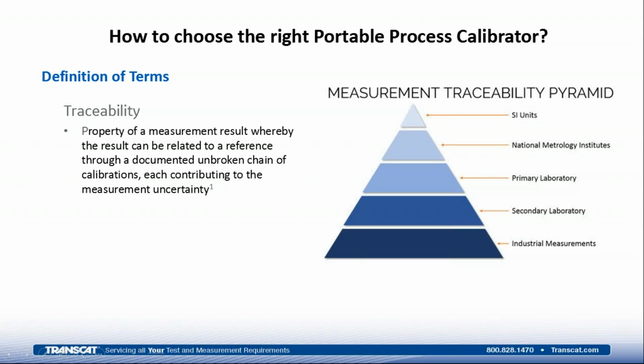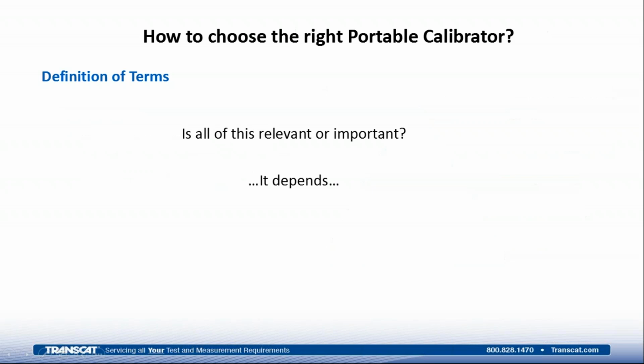Now, those units and devices will be calibrated against other calibration devices that are transfer standards or higher accuracy standards. So secondary laboratory, primary laboratory, up to national metrology institutes. So it is possible to keep a documented unbroken chain of those calibrations by tracing that calibration.